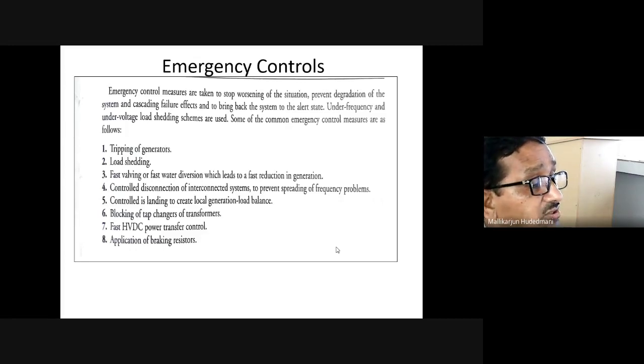Tripping of generator. Suppose a situation where a heavy load is noticed, a very big fault has really caused a massive fault, and power is flowing down to the earth. Definitely this will spoil transmission, equipment, the generator, like that. So, tripping of generator: cut off the generator so that at least the generator is protected from such hazards. What things got lost, let them be lost. At least the tripping of generator prevents generator failure.